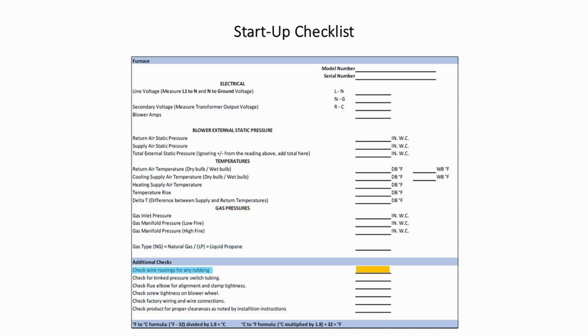Under additional checks, check wire routing for any rubbing. Check for kinked pressure switch tubing. Check flue elbow for alignment and clamp tightness. Check the screw tightness on the blower wheel. Check factory wiring and wire connections. Check the product for proper clearances as noted by the installation instructions.